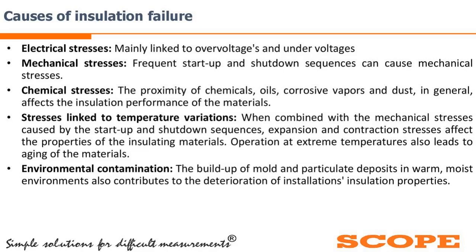Operation at extreme temperature also leads to aging of the material, so this is also a main cause of insulation failure. Similarly, environmental effects, that is the buildup of mold and particulate deposits in warm and moist environments, will cause insulation failure. So these are the main causes of insulation failures.